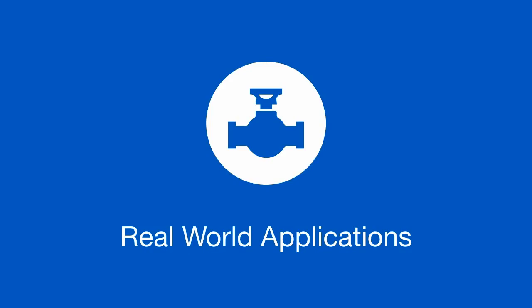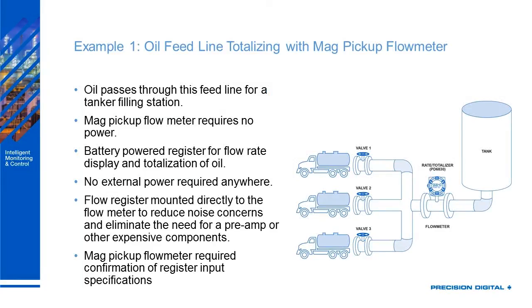So now that we've discussed the pros and cons, let's take a look at some real-world applications that show you where pulse signals can really shine. The first one is on an oil feed line coming out of a storage tank that uses a mag pickup flow meter to totalize everything going through that line to a couple of different filling stations.